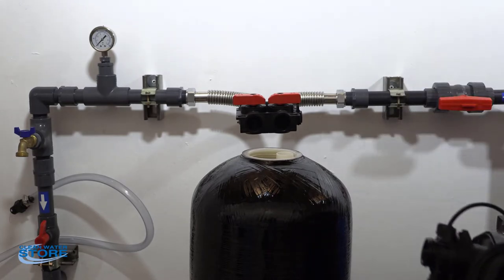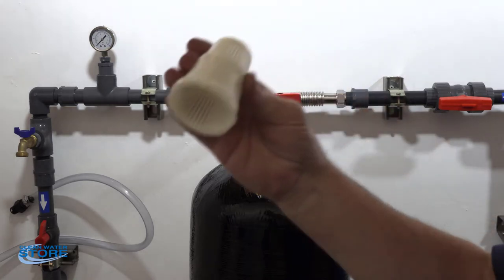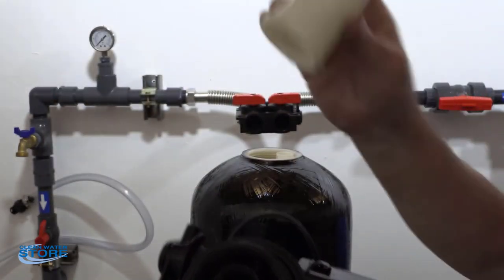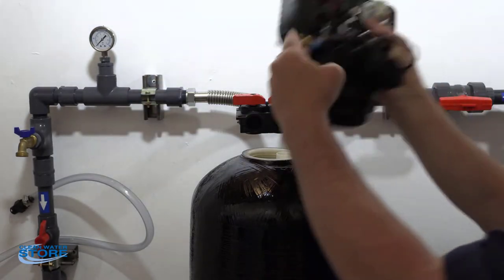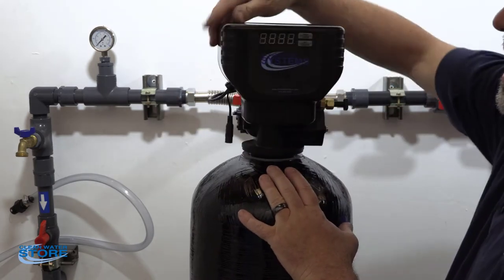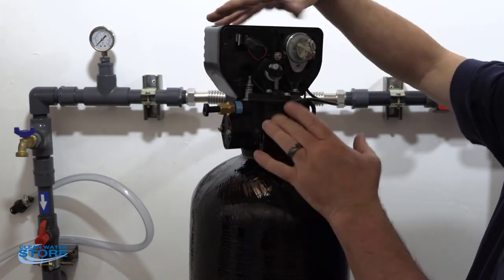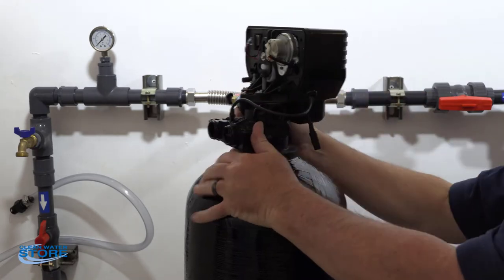If you have a ProOx or ChemSorb, you're going to have a top filter that snaps in there. In this case we don't have it, but in some cases you will. Go ahead and get that D-tube seated and thread this on — hand tight. You want to get the O-ring sealed, but you don't want to crack the valve body and you don't want to crack the tank. So just give it a good tightening.